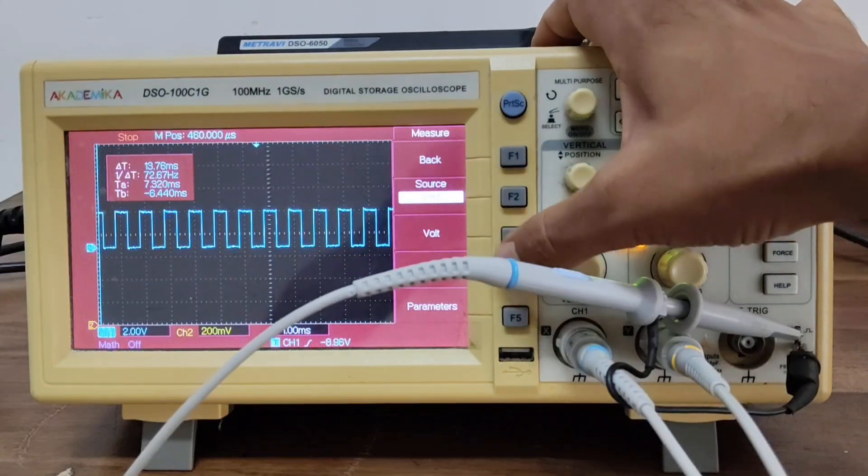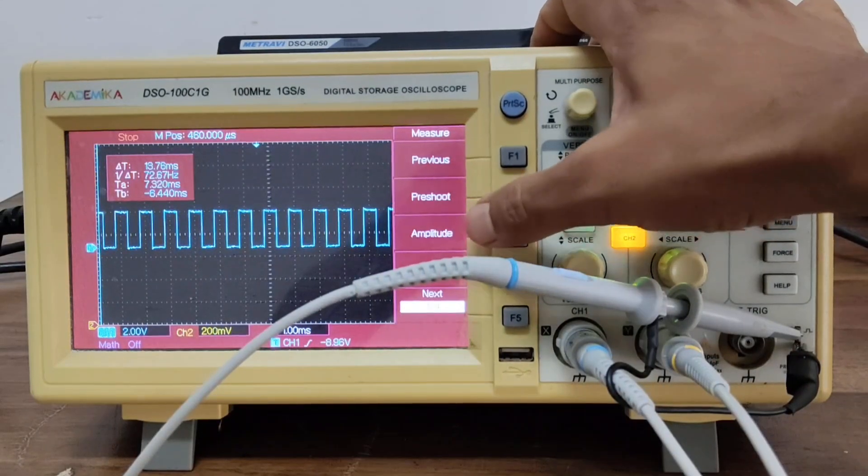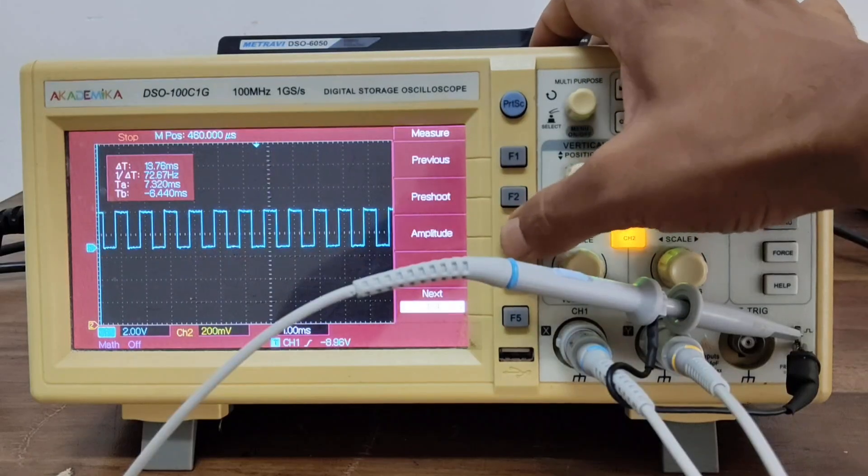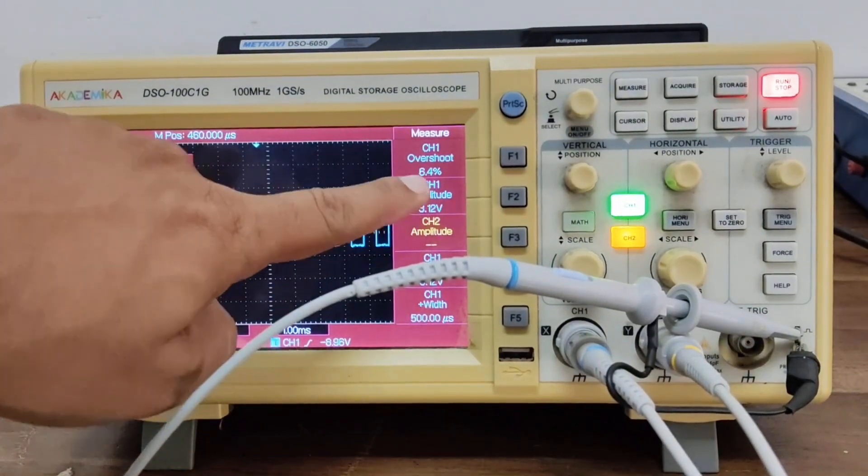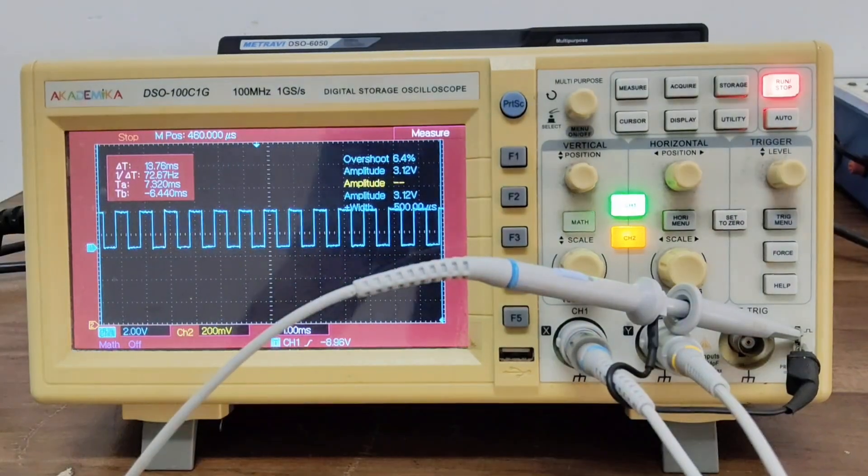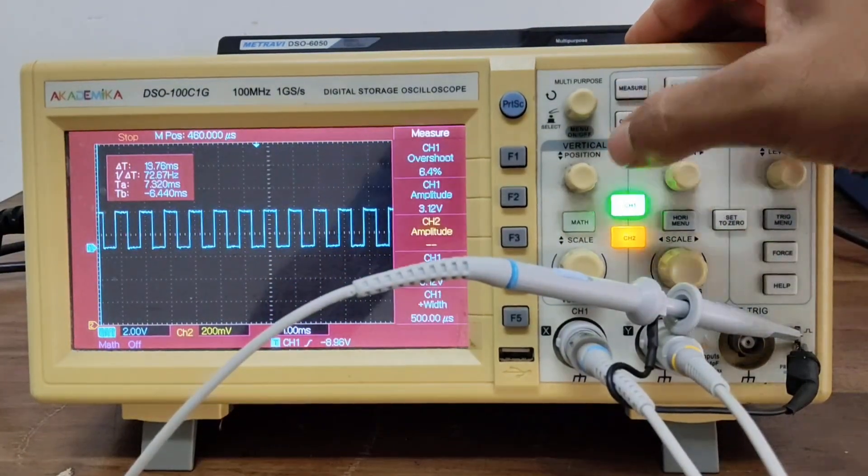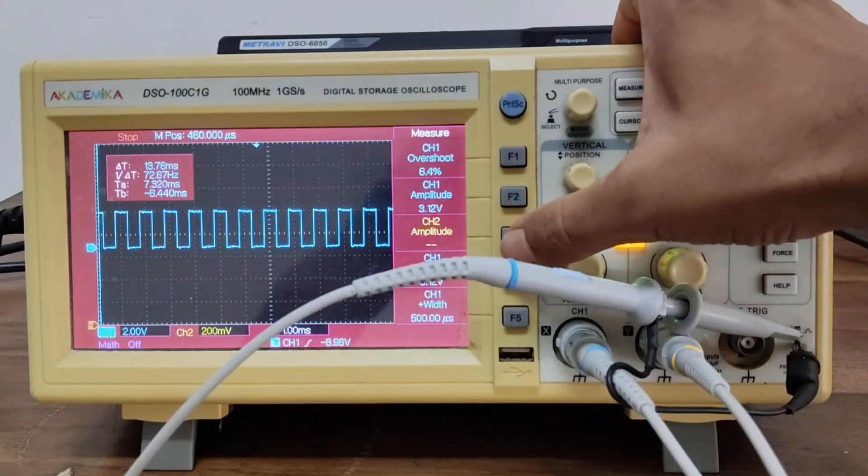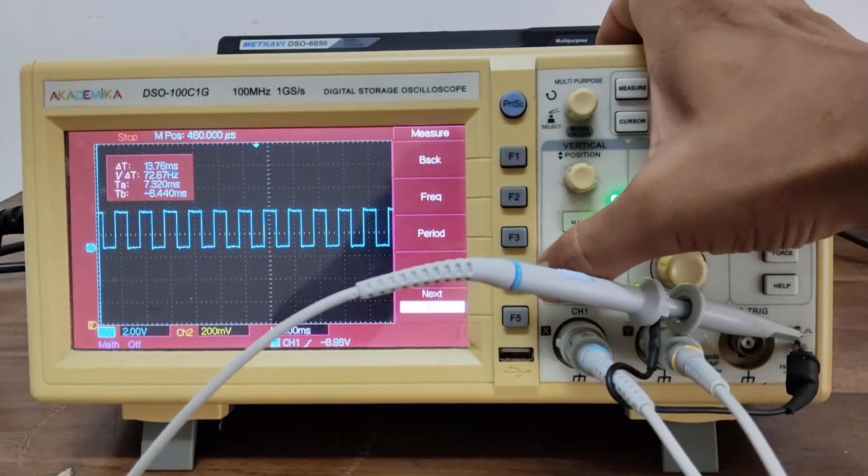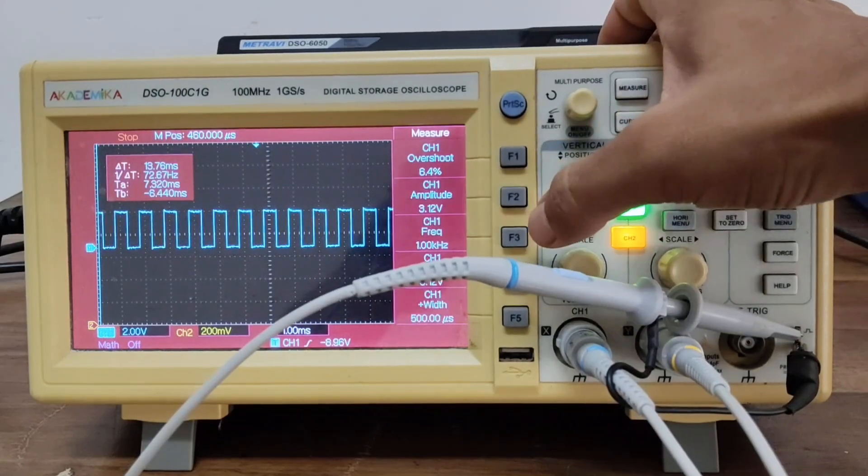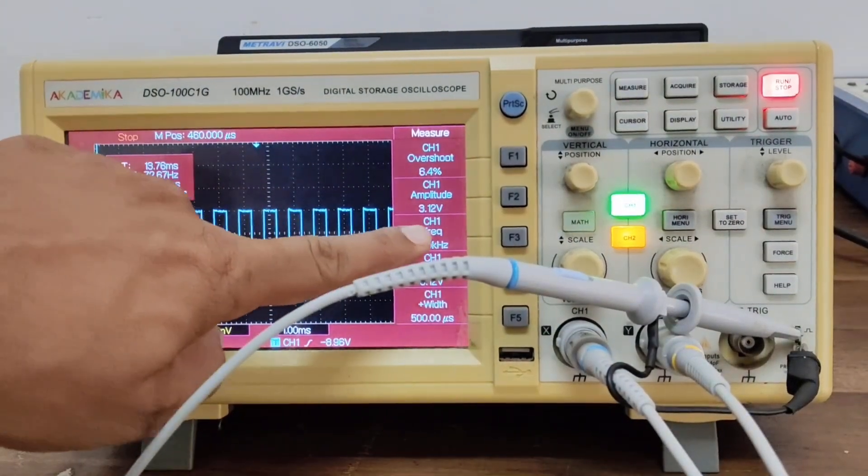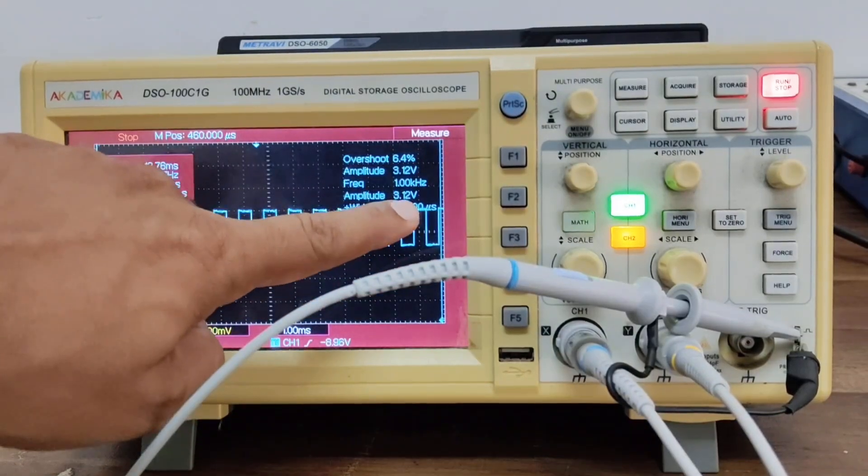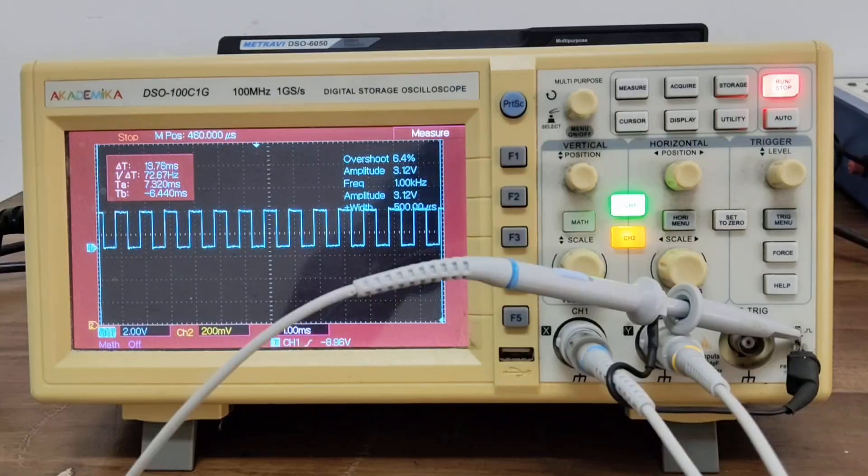Then I will take the voltage. Then I will press this. Then I will get the voltage for amplitude. I will take this. So you can see that the amplitude of channel 1 is given here. If I want to get the time, then using this button you can use for time. I will select here. You can press this knob and you will get the frequency directly from here. Look here, the channel 1 frequency is 1 kilohertz, amplitude is 3.12 volts. And like this you can measure the parameters of a signal.